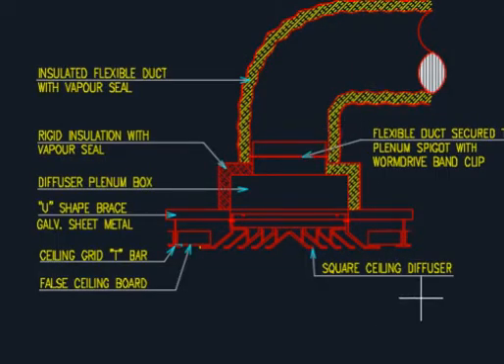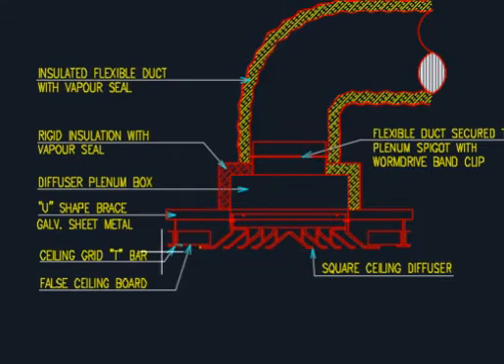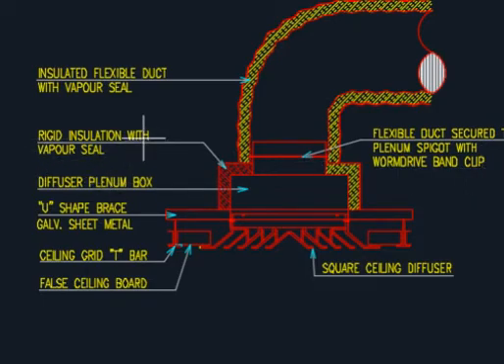So first I will start with the diffuser. This is a simple diffuser here. This is always installed horizontal, not vertical — it is installed in the ceiling. This is a flexible duct coming here from the main duct. The flexible duct comes to the plenum box, and this is the diffuser — air will be thrown from here. This flexible duct must be insulated, as somebody asked me a question before. This is an insulated flexible duct. This is a rigid insulation with vapor seals, and this is the diffuser plenum box.